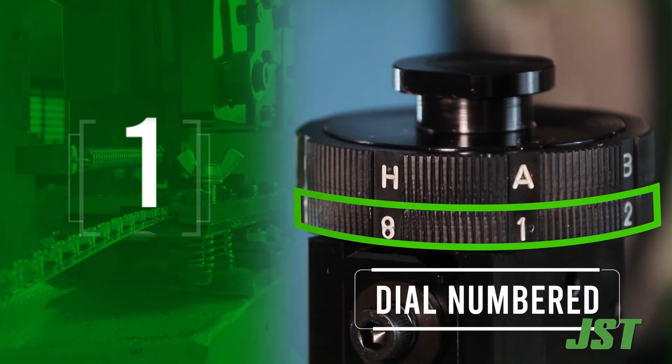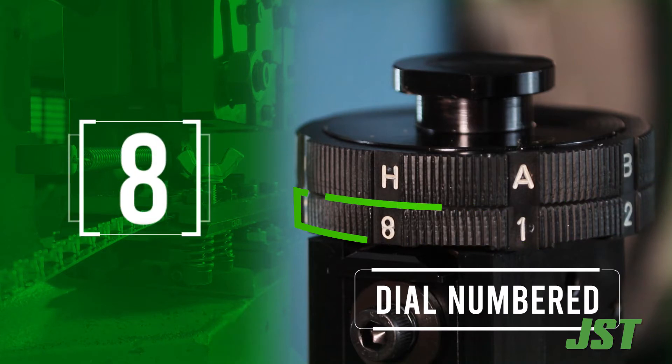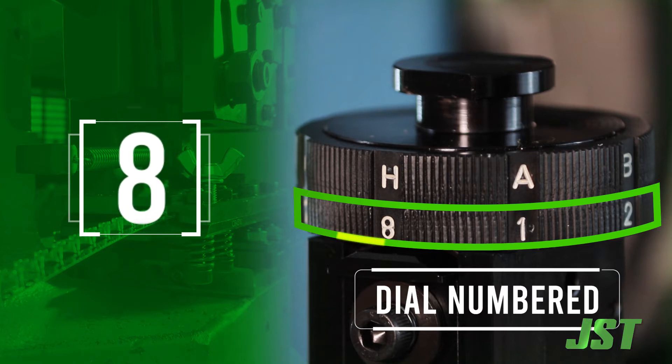The dial numbered from 1 to 8 is for adjusting the crimp height of the insulation. 8 is the highest setting and should always be the starting point.